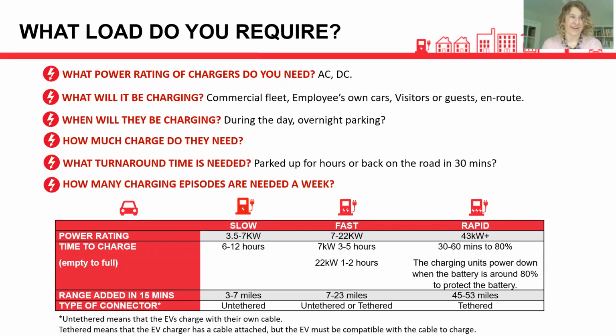So, load. This is the pivotal question. I have conversations with clients and they might be looking, for example, for 3 22 kilowatt chargers. Now, these 22 kilowatt chargers might have 2 sockets, and each of the sockets might be able to pull 22 kilowatts each. So suddenly you're looking at 44 kilowatts per charger. You multiply that by 3 and you get 132 kilowatts. It can all add up very rapidly.